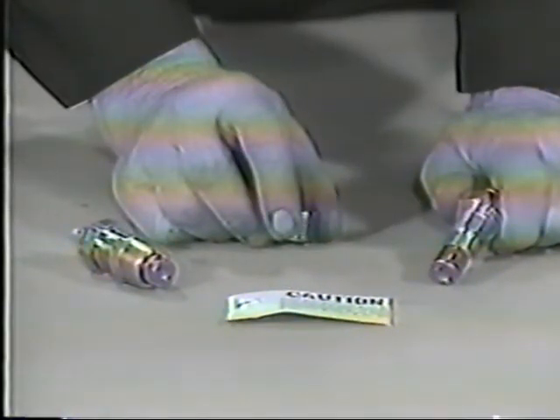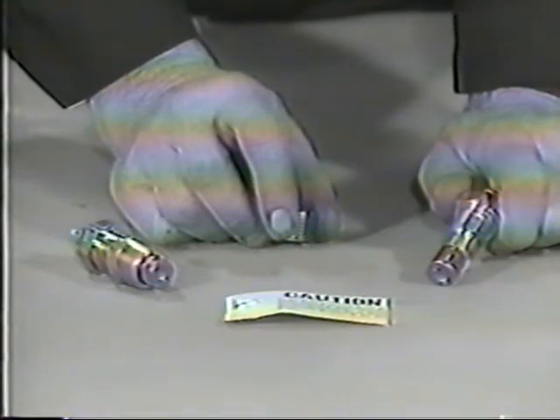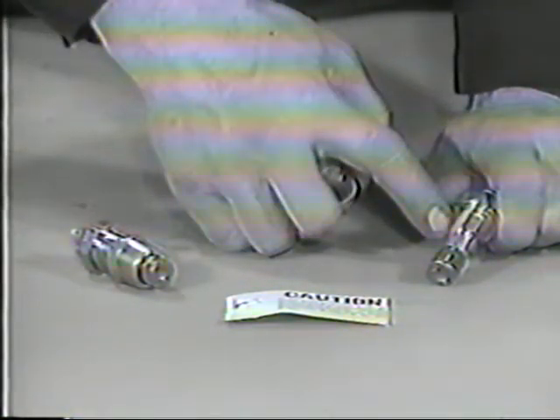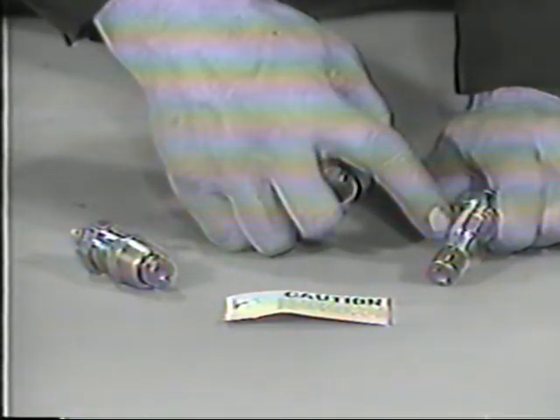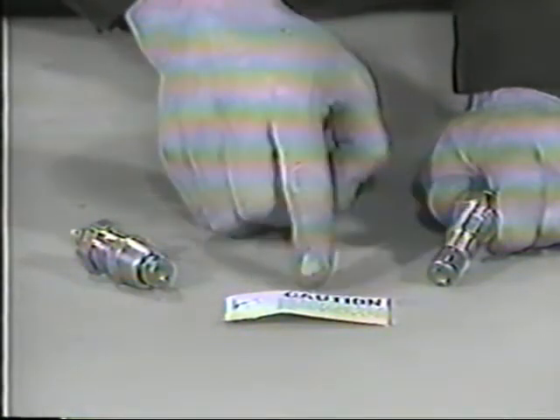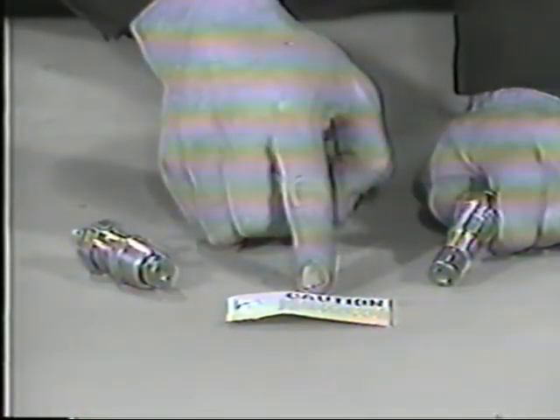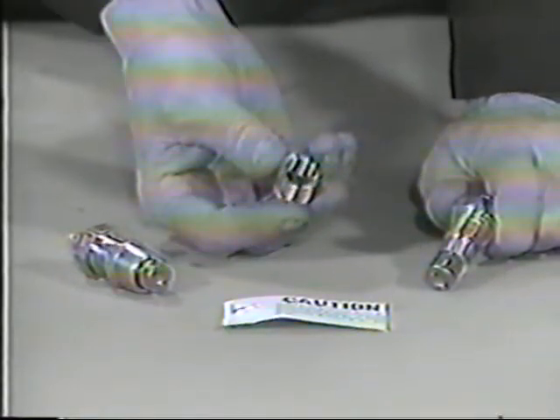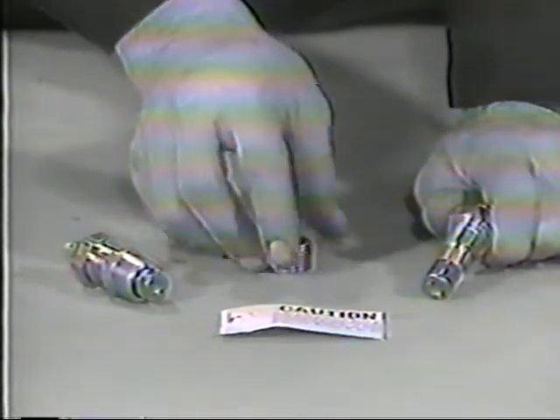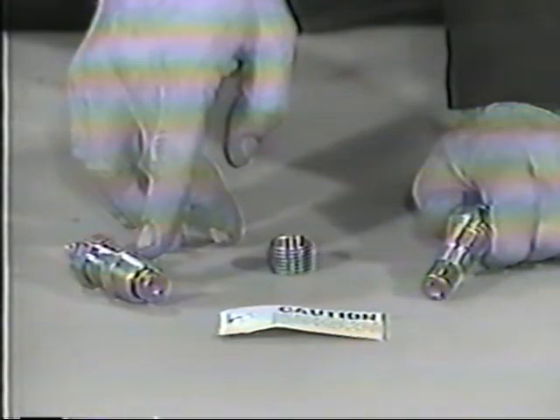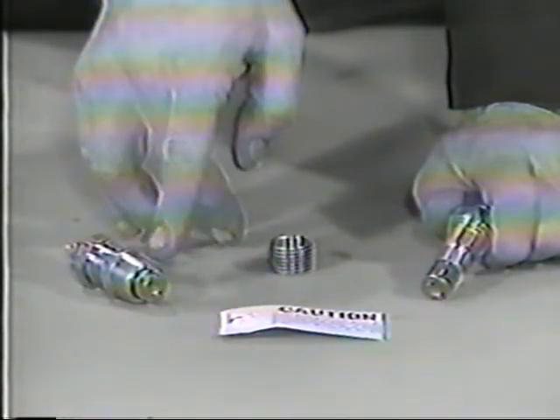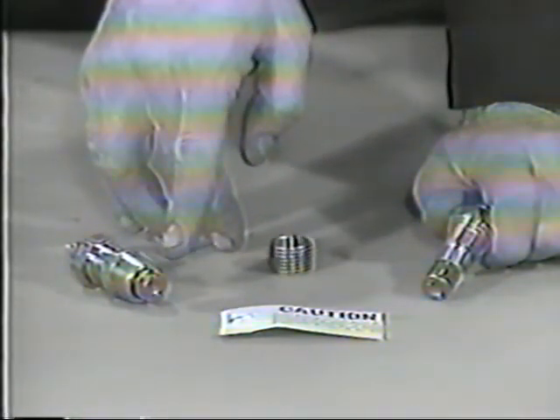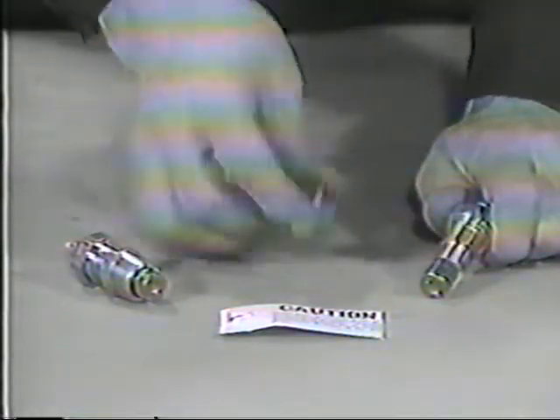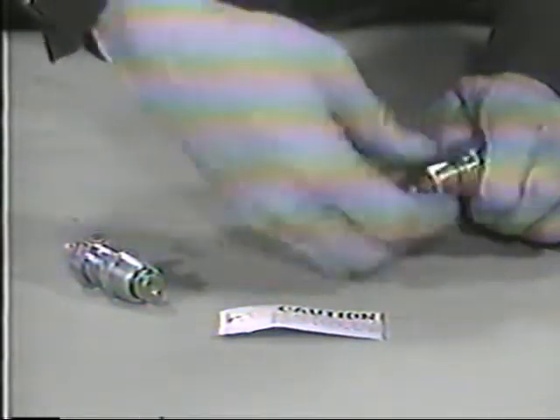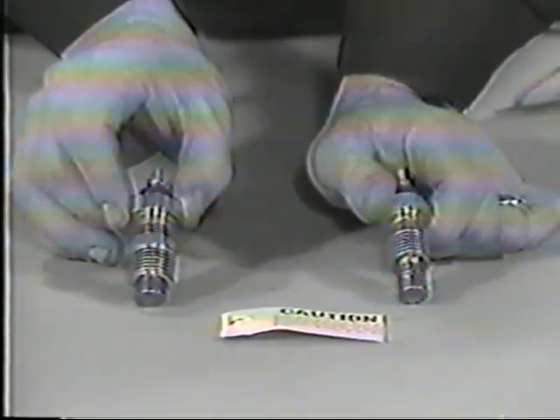The sixth troubleshooting area concerns mounting the alarm stat. The alarm stat has a 3/8 inch pipe thread, and if you need to mount it in a 1/2 inch pipe hole, a warning tag shipped with every alarm stat tells you that a special bushing is required. This is important. If you use a standard reducing bushing like this one, the stat will not be submerged deeply enough to accurately sense the coolant temperature. Notice how the correct KYSOR bushing does not affect the installed depth.